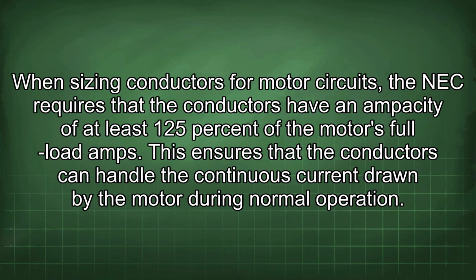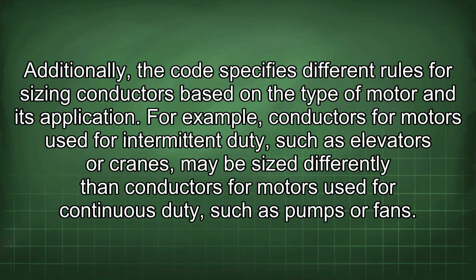When sizing conductors for motor circuits, the NEC requires that the conductors have an ampacity of at least 125% of the motor's full load amps. This ensures that the conductors can handle the continuous current drawn by the motor during normal operation. Additionally, the code specifies different rules for sizing conductors based on the type of motor and its application. For example, conductors for motors used for intermittent duty, such as elevators or cranes, may be sized differently than conductors for motors used for continuous duty, such as pumps or fans.